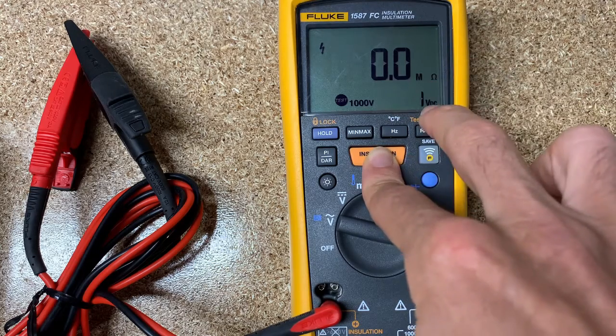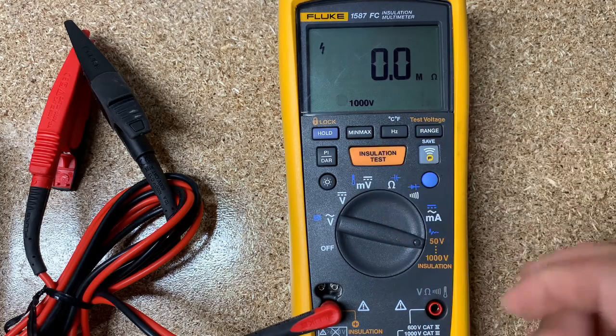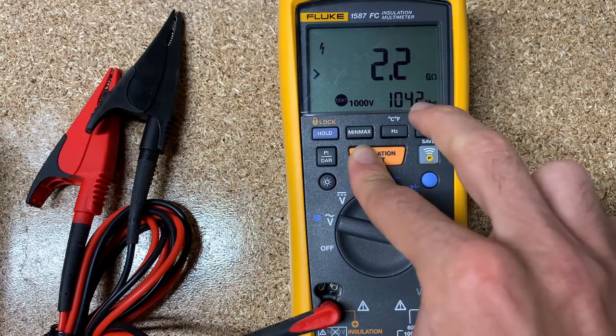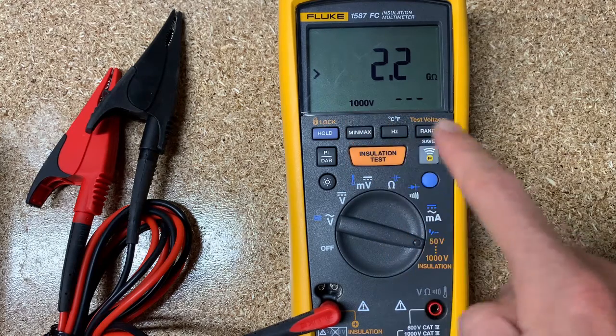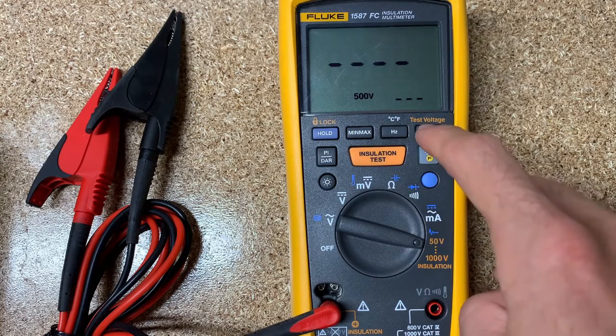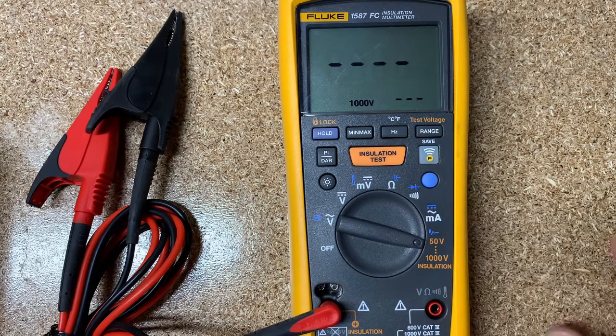With no resistance it doesn't go above one volt because once it detects a short it kind of stops. But if I take this off so there's no continuity and hit that button, you can see the test voltage goes up to a thousand volts. If you didn't want to test at a thousand volts, you can change the test voltage by clicking this button — 50, 100, 250, 500, or 1000 volts — and that's as high as you can go with the 1587 FC.